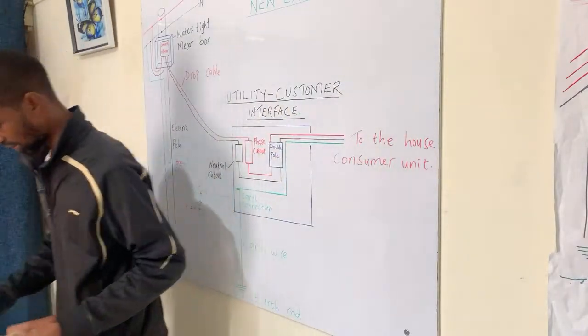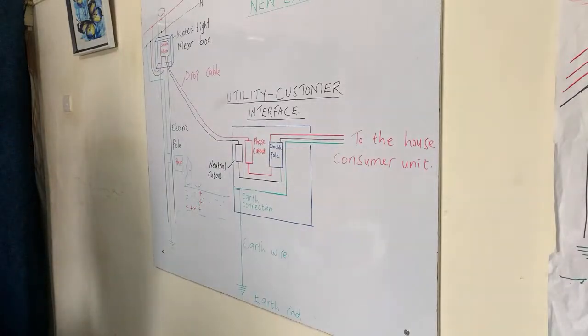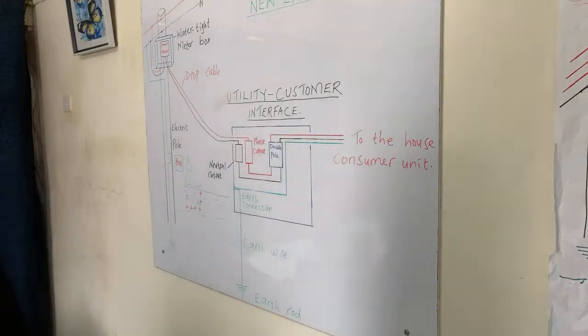So let me just get into the consumer unit and show you also another feature of the earthing connection. And the earth connection is never interrupted the same way the neutral connection is never interrupted when you connect a neutral through the MCB, or that is the double pole MCB, which serves as the main switch to the customer, or at the meter box where you have that connection. You must ensure that that connection is never interrupted.